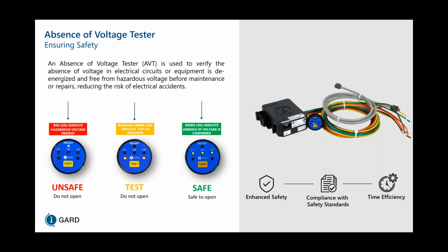In doing this additional connection to the phases, what we can do is ensure that the absence of voltage tester is properly connected and has continuity. So we inject a small level of current through one of the leads, and as long as that signal comes back on the other lead, we can confirm that we're still connected to the 3 phases as well as to ground.